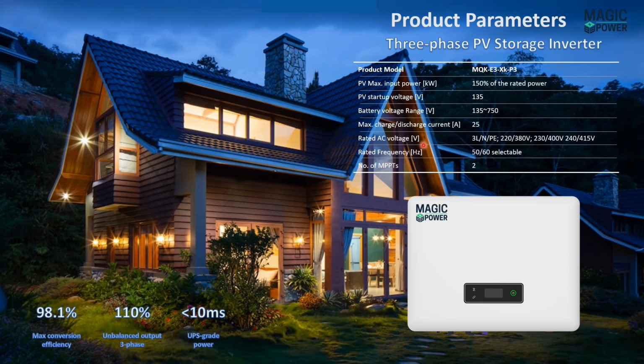Some product parameters. The product model comes with the company name, the series, and XK, where X represents the rated power of the system, and P3 means the system is three phase. The maximum PV input power is 150% of the rated power of the system, as I mentioned earlier. The startup voltage for the PV and battery is 135. Charging and discharging current is 25 ampere. Rated AC voltage could be 380, 400, and 415 depending on the grid standard. Similarly, the frequency is selectable, and there are two MPPTs for this system.